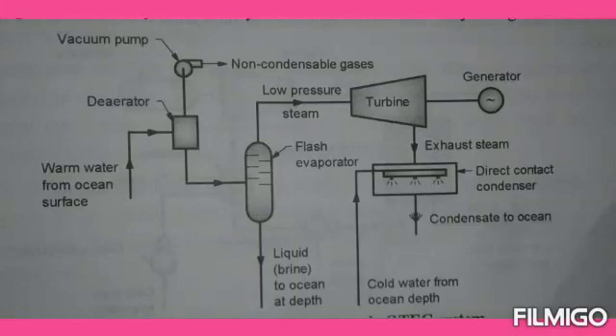That low pressure steam is passed through the turbine where expansion of the steam takes place. After expansion, mechanical energy is generated, which is converted into electrical energy in the generator. The exhaust steam is then supplied to a direct contact type condenser, where it is cooled by cold water from the ocean depth. When the cold water and exhaust steam come into contact with each other, the exhaust steam gets condensed and the condensate is released back to the ocean.